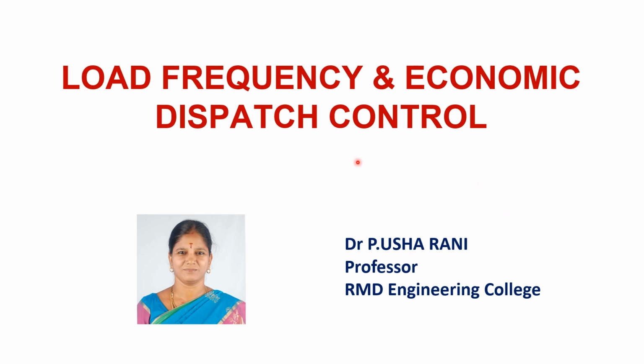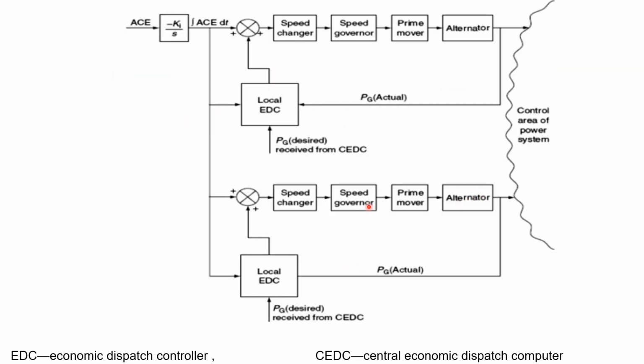I'm going to brief about the topic of load frequency control and economic dispatch control. Generally, load frequency control with the integral controller, if you take care, we can get a zero steady state frequency error. That is, a steady state frequency error of zero, and a fast dynamic response. You can say within a few seconds, LFC is a fast acting controller.